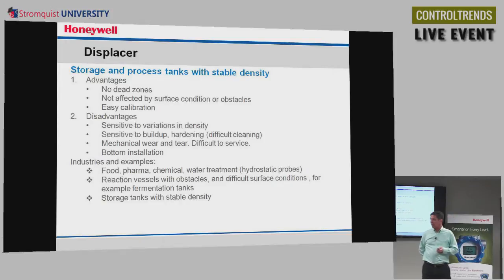Advantages, disadvantages. The advantage, there's no dead zone. It's not affected by surface conditions or obstacles. Pretty easy to calibrate. But the concerns would be with variations in density. So this is another one that's set up around density. It's got to be what the assumed value is. And it's a mechanical device, so it's susceptible to buildup and hardening, and over time you get this mechanical wear and tear, and that affects the calibration, affects the accuracy of the reading. This one's also a bottom installation, and it's fairly common in some food, pharmaceutical, chemicals kind of applications, reactors in chemical plants, also refineries. Pretty common is across a distillation column, measuring the level within those trays on distillation columns.